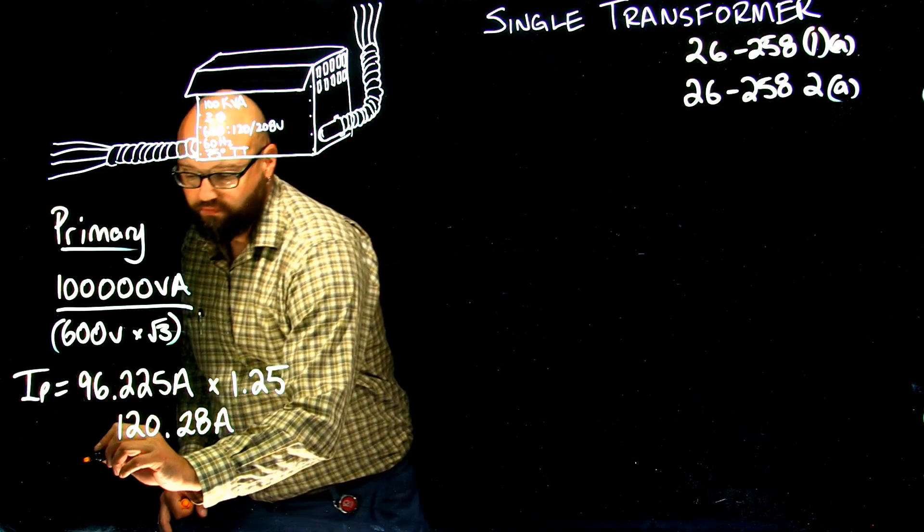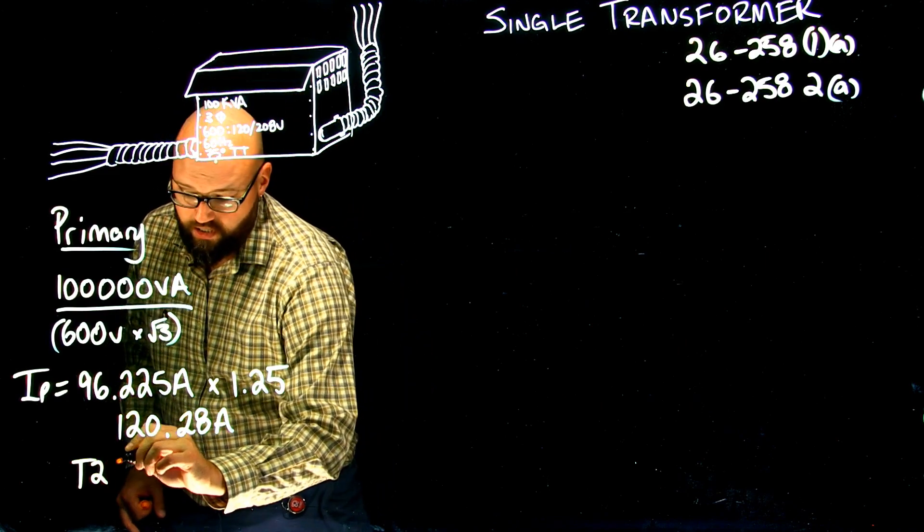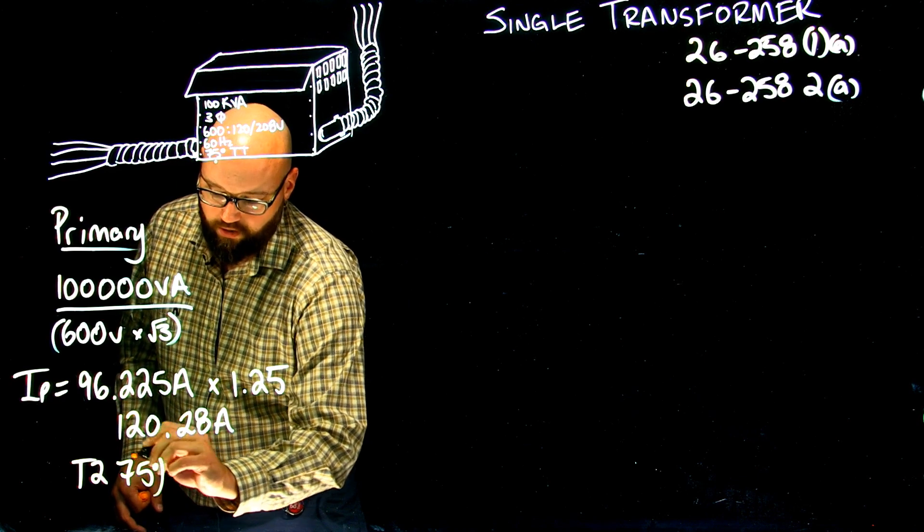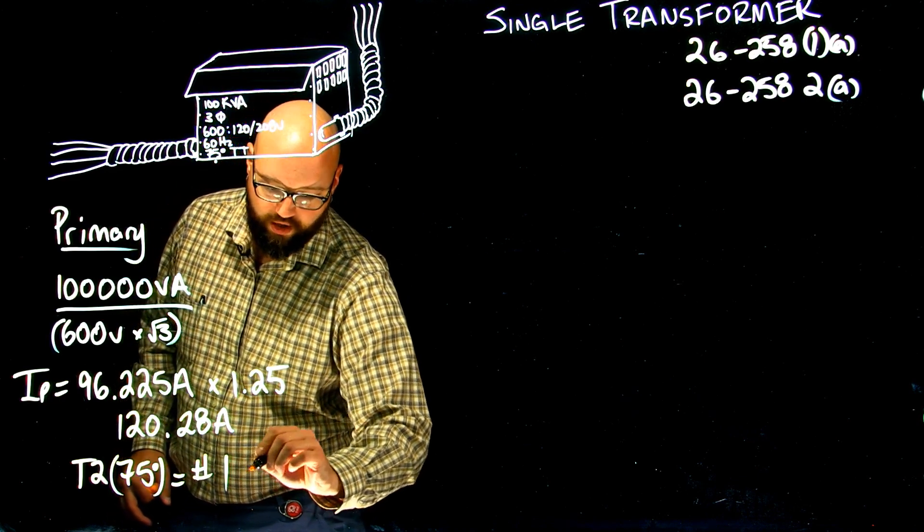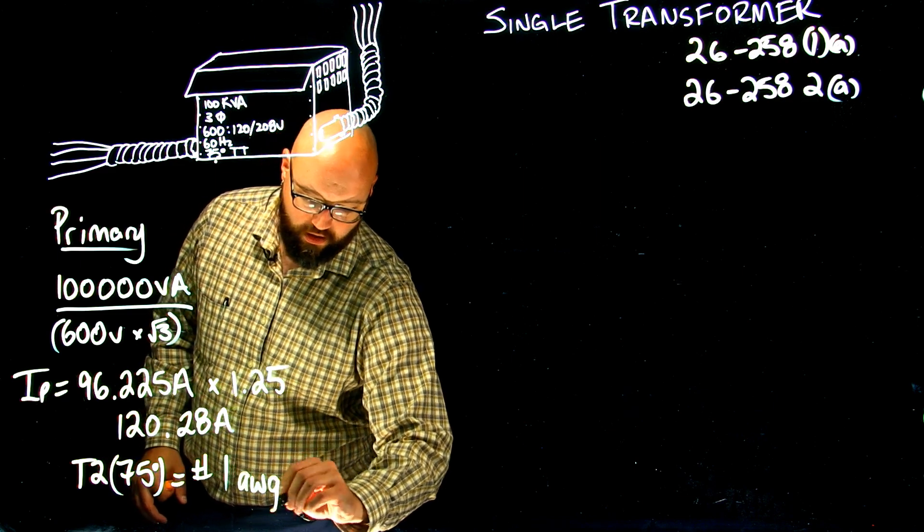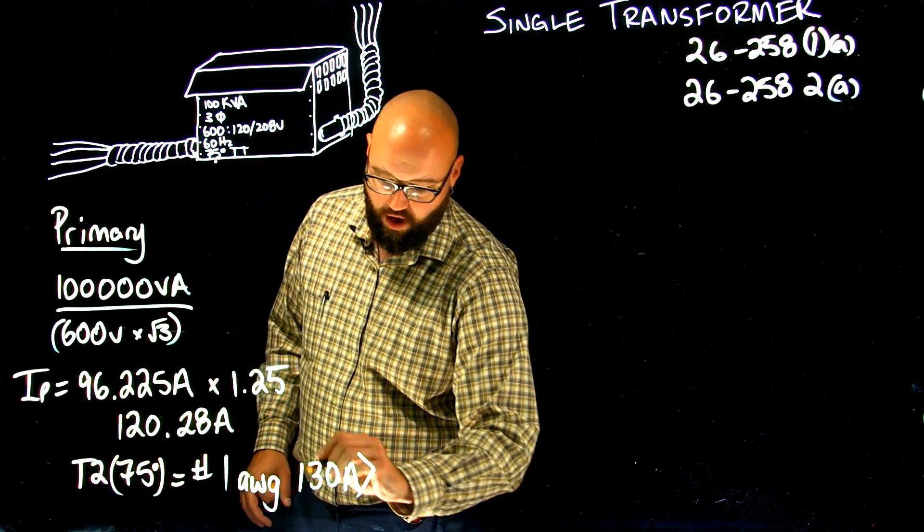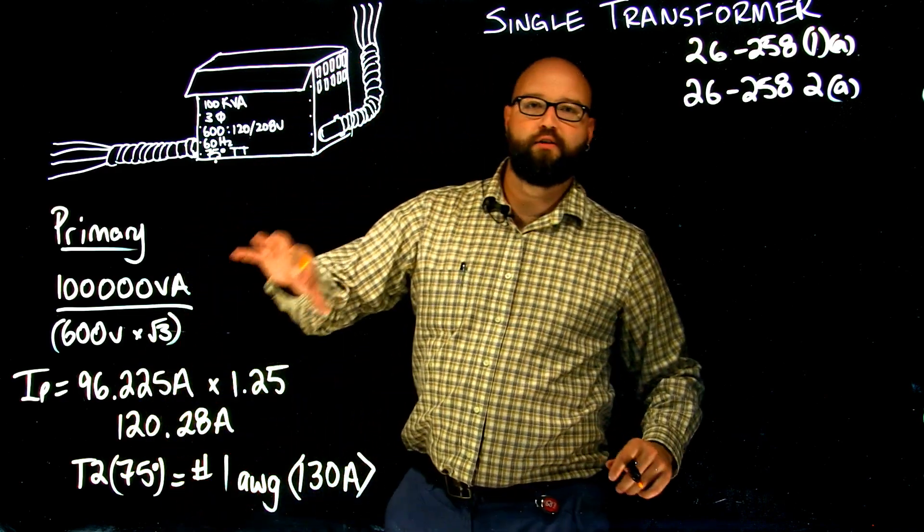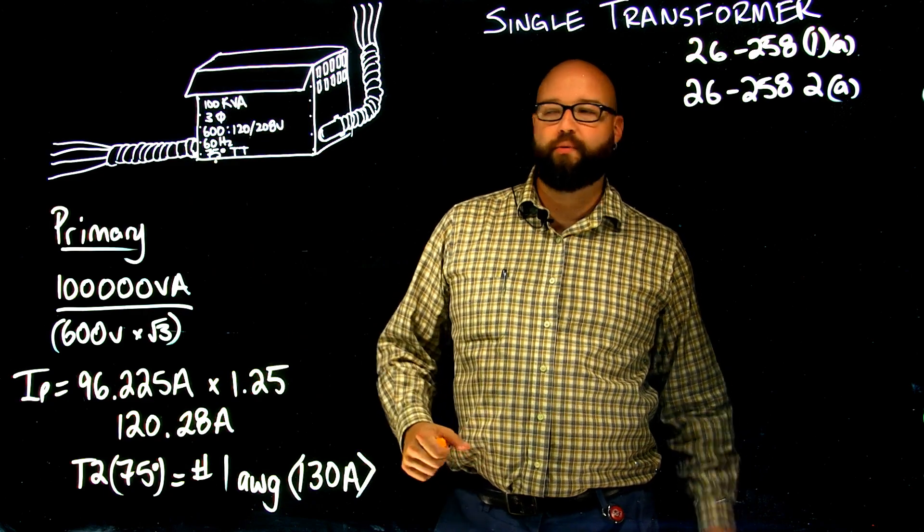So, we're going to go to table 2, and because of 75-degree termination, we're going to go in the 75-degree column. We're going to choose a number 1 gauge conductor with an ampacity of 130 amps. There's our primary conductors feeding the primary side of our transformer.